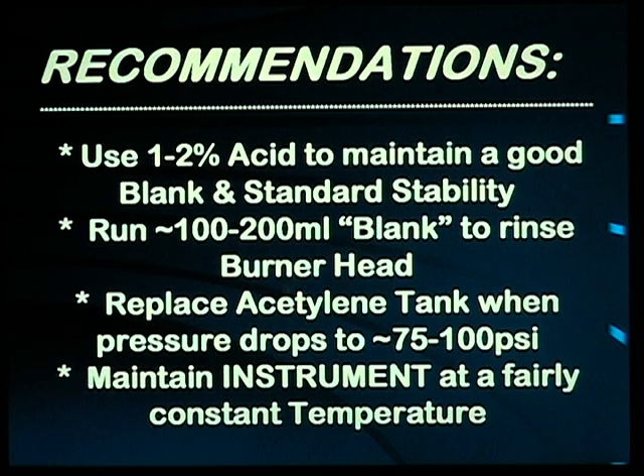It is highly recommended that your acetylene fuel tank be replaced when the pressure on the cylinder drops to approximately 75 or 100 psi, or the acetone that is used to prepare the acetylene under pressure may damage your flow meters. Maintain the instrument at a fairly constant temperature for good wavelength stability. Otherwise, frequent recalibration of the wavelength setting may be needed.